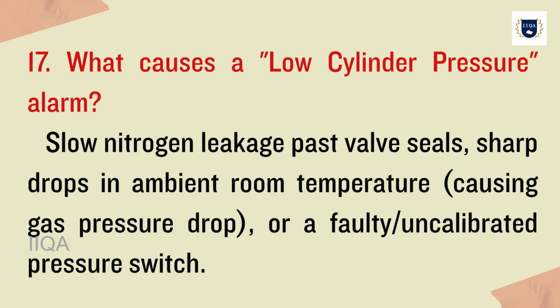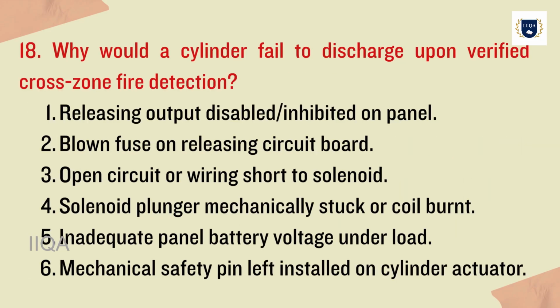17. What causes a low cylinder pressure alarm? Slow nitrogen leakage past valve seals, sharp drops in ambient room temperature causing gas pressure drop, or a faulty, uncalibrated pressure switch.